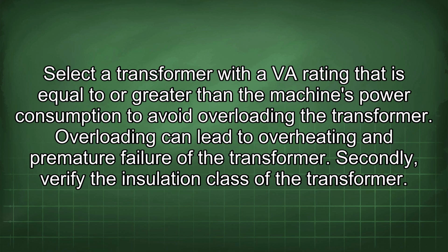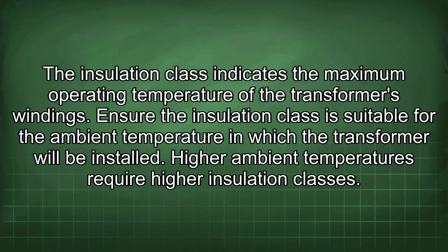Secondly, verify the insulation class of the transformer. The insulation class indicates the maximum operating temperature of the transformer's windings. Ensure the insulation class is suitable for the ambient temperature in which the transformer will be installed. Higher ambient temperatures require higher insulation classes.